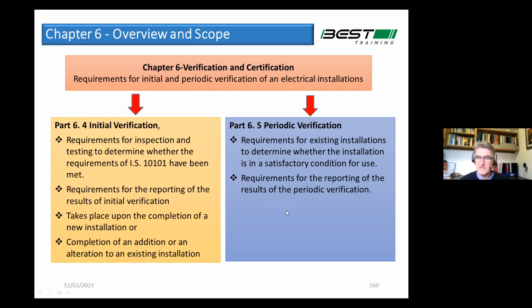And then periodic verification, really a funny area. It tells us every year, visual inspection of buildings, and every somewhere between 3 years and 5 years, depending on the nature of the building, we should be carrying out periodic verification, which is really telling us we should be going back and repeating the tests that we've carried out at the initial verification. In reality, nobody does that, and it's probably an area that does need to be addressed going forward.